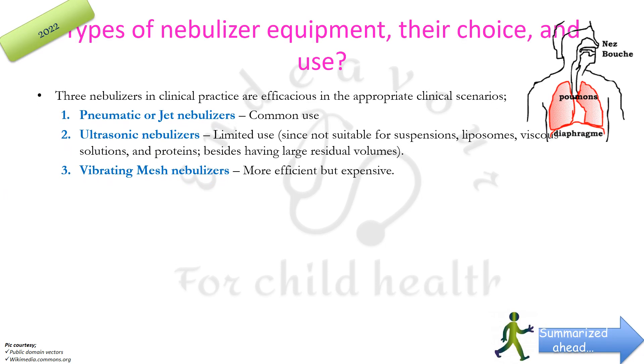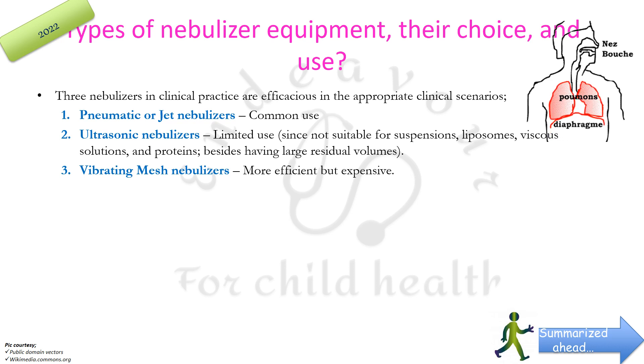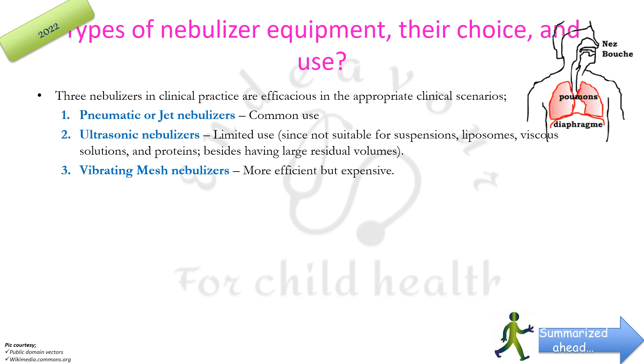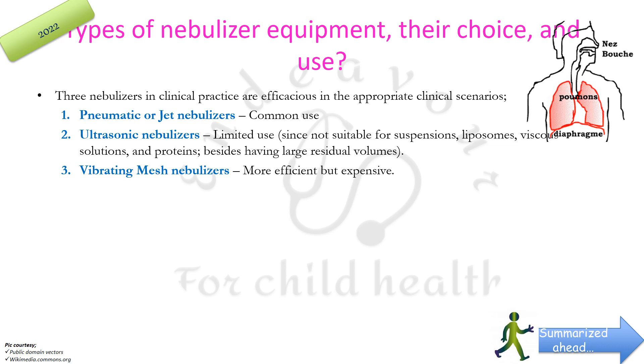There are three types of nebulizers. The first and most commonly used is the pneumatic or jet nebulizer. The second type is ultrasonic nebulizers, which have limited use since they are not suitable for suspensions, liposomes, viscous solutions, and proteins, and also have large residual volumes.